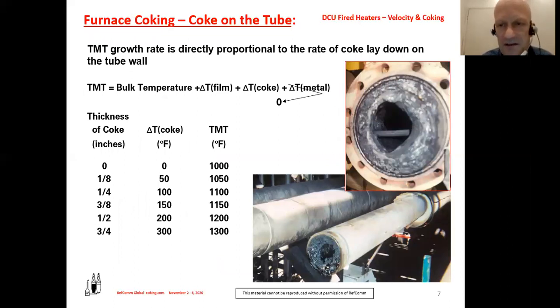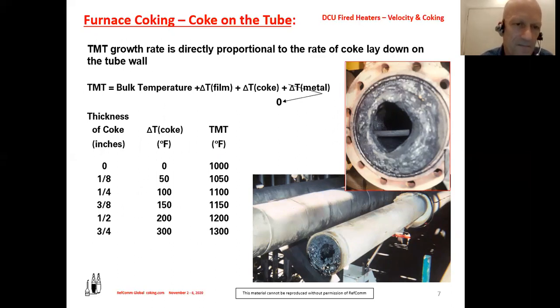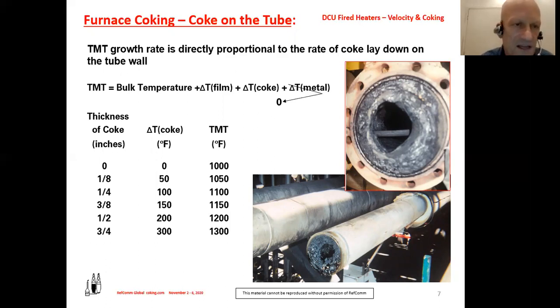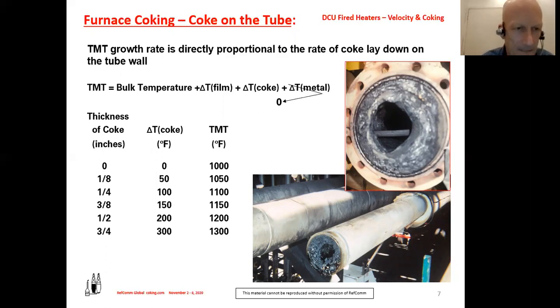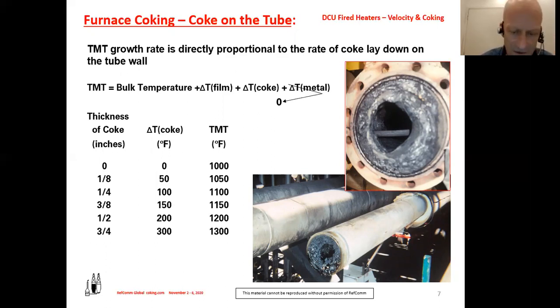A table shows the effect of coke thickness on tube metal temperature. The TMT is essentially the bulk temperature plus the delta T across the film, plus the delta T across the coke, plus the delta T across the metal. As coke thickness increases from zero to three-quarters of an inch, tube metal temperature rises from approximately 1000 to 1300°F.